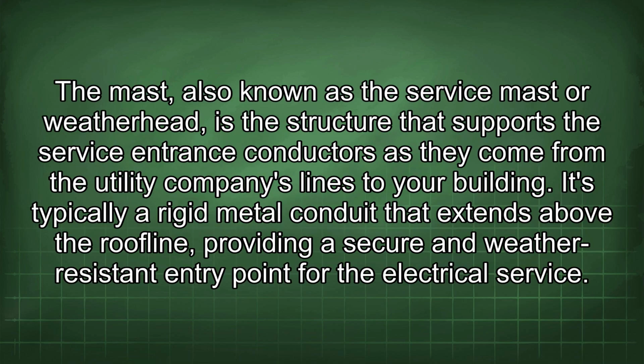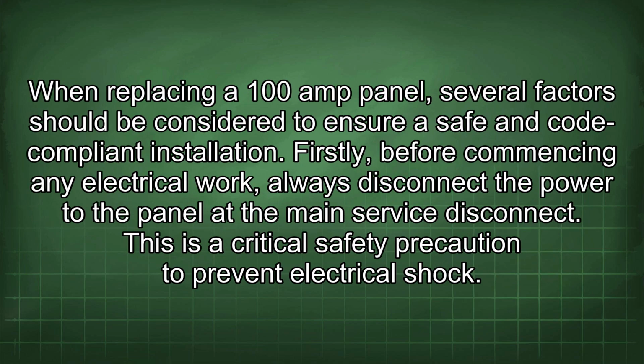The mast, also known as the service mast or weatherhead, is the structure that supports the service entrance conductors as they come from the utility company's lines to your building. It's typically a rigid metal conduit that extends above the roof line, providing a secure and weather-resistant entry point for the electrical service. When replacing a 100 amp panel, several factors should be considered to ensure a safe and code-compliant installation. Firstly, before commencing any electrical work, always disconnect the power to the panel at the main service disconnect. This is a critical safety precaution to prevent electrical shock.